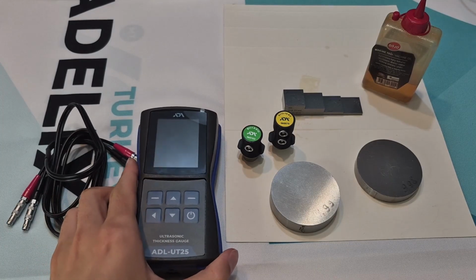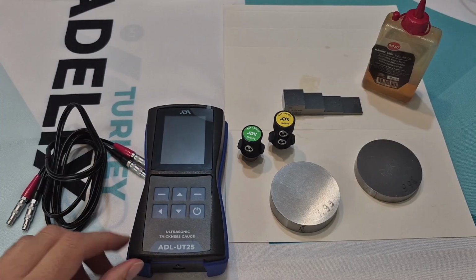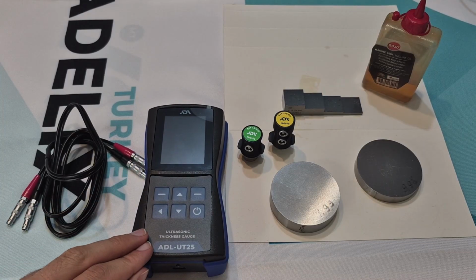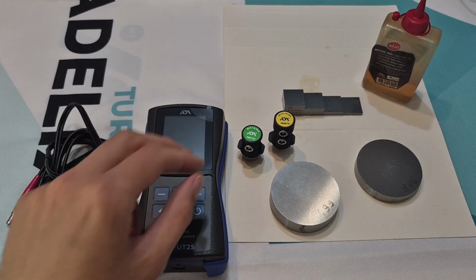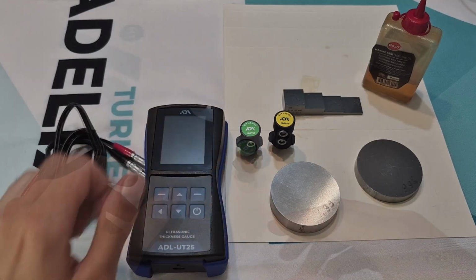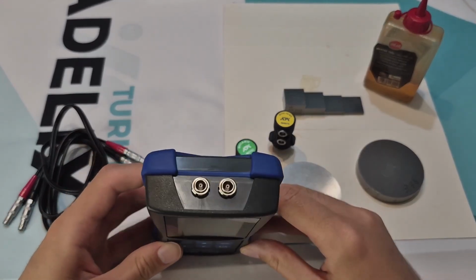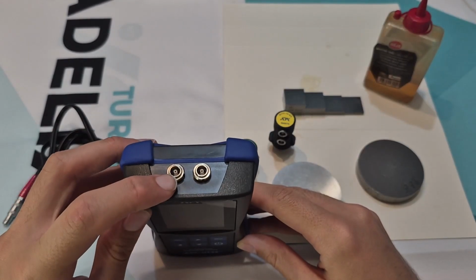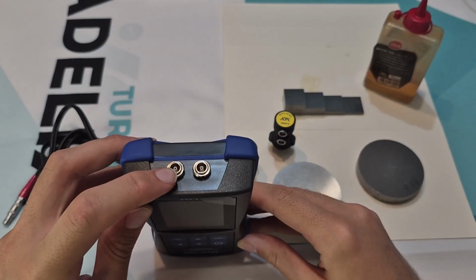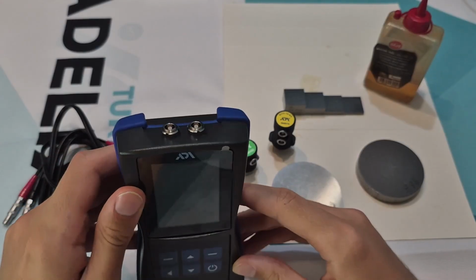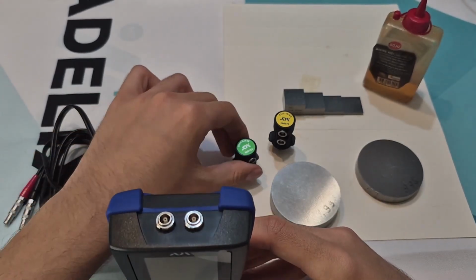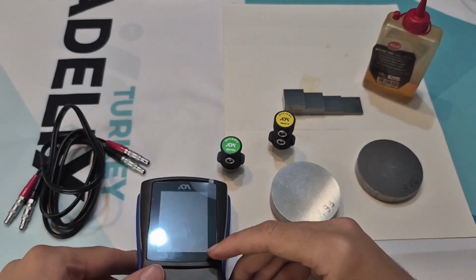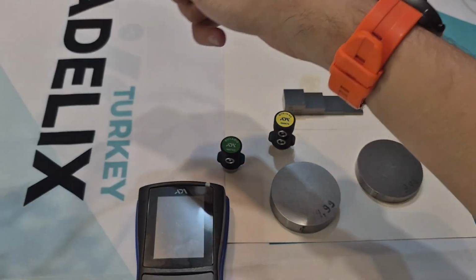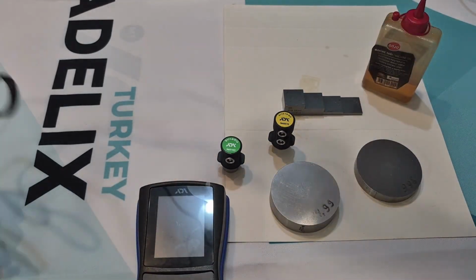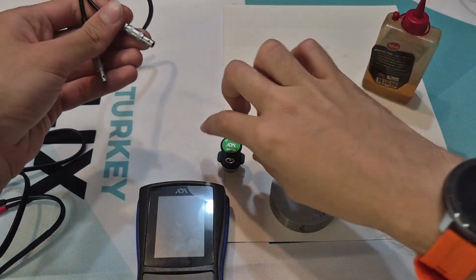Two types of direct ultrasonic transducers are used with the ADL-UT25, single crystal and dual crystal. Let us take a look at the device. The left connector is the transmitter, the right connector is the receiver. If a single crystal transducer is used, it is enough to connect it to the transmitter connector. We connect one end of the cable to the transducer and the other end to the transmitter connector. We use a cable of the same color.